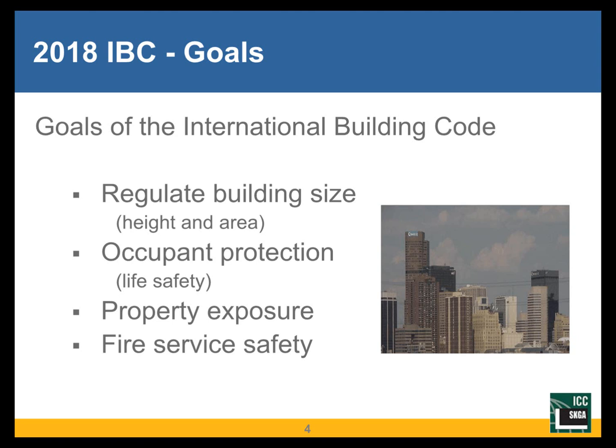A third item is property exposure. As we build these buildings, they pose a fire risk not only to the building itself and to the occupants, but to adjacent properties. And as I mentioned when talking about regulating the size of the building — as the building gets bigger, it can in fact pose a bigger risk to adjacent properties. So the building code has provisions from a fire safety and fire resistance point of view that want to reduce or minimize the risk of fire spread from the building in question to any adjacent properties.